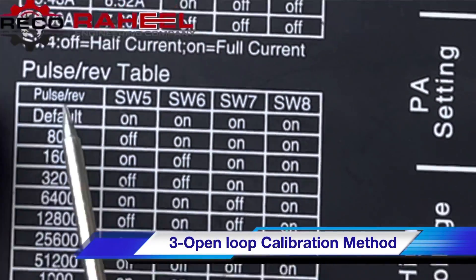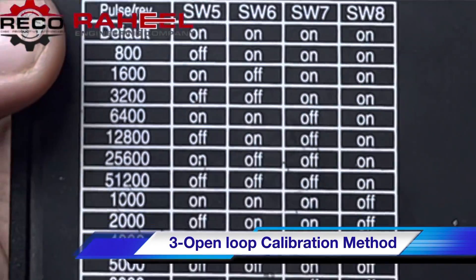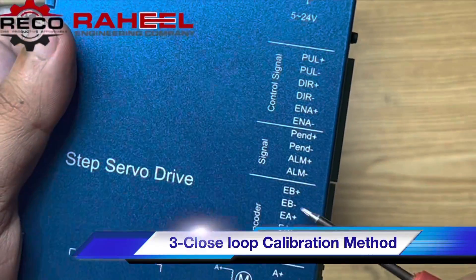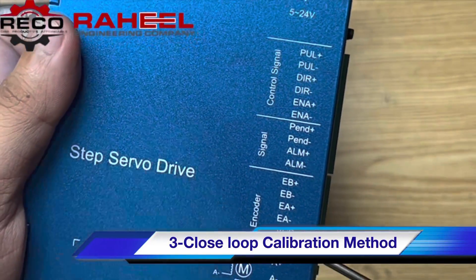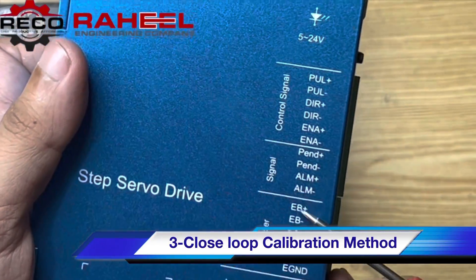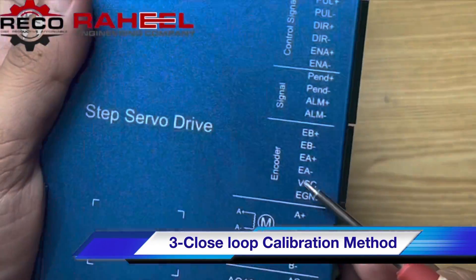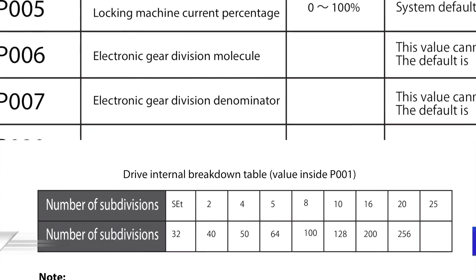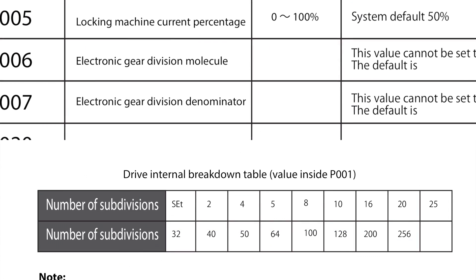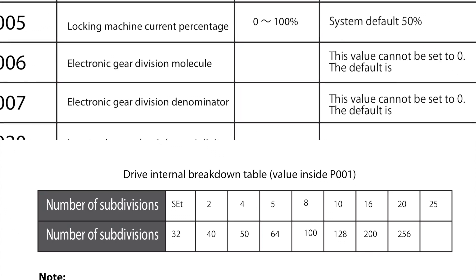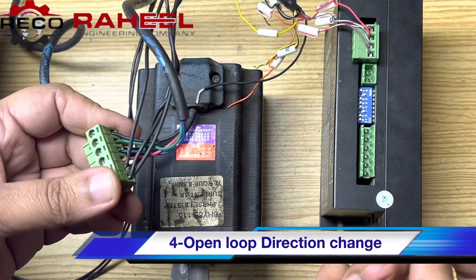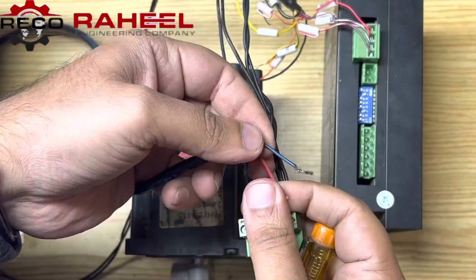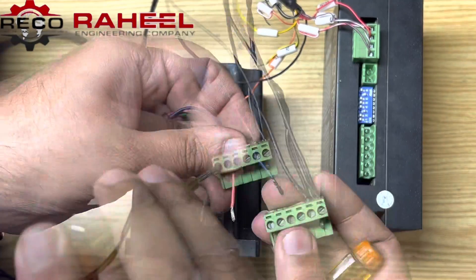Open loop calibration setting is done by DIP switch according to the pulse-per-revolution table. Closed loop calibration setting is done by two methods: the first method is step setting, and the second method is electronic gear ratio setting through parameters. Both types of parameters can be seen on the screen.